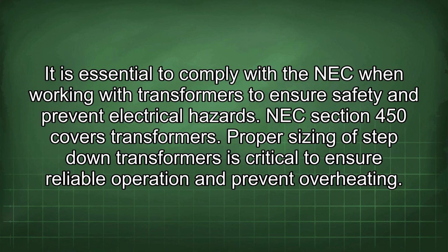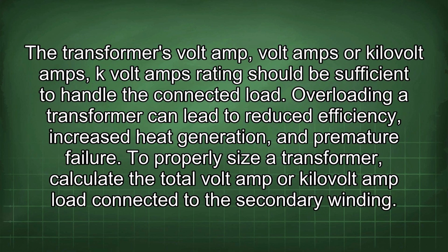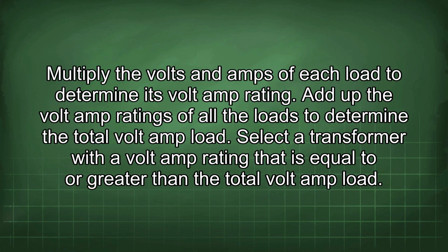Proper sizing of step-down transformers is critical to ensure reliable operation and prevent overheating. The transformer's volt amps or kilovolt amps (kVA) rating should be sufficient to handle the connected load. Overloading a transformer can lead to reduced efficiency, increased heat generation, and premature failure. To properly size a transformer, calculate the total volt amp or kilovolt amp load connected to the secondary winding. Multiply the volts and amps of each load to determine its volt amp rating. Add up the volt amp ratings of all the loads to determine the total volt amp load. Select a transformer with a volt amp rating that is equal to or greater than the total volt amp load.